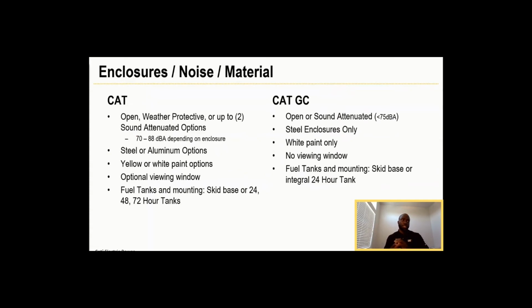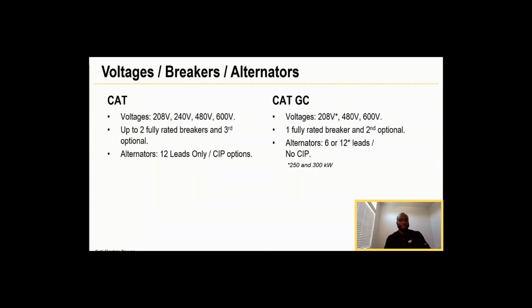On our fuel tanks, we see that the vast majority of North America's requirements, especially in the bid-spec world, usually concern tanks. That is either skid-based or a 24-hour tank available with the CAT GC product. With our traditional CAT product from the factory, you can get 24, 48, or 72-hour, and in some cases a 660-gallon tank as well. But if you're looking for something more or less than that, please contact your local dealer, as dealers have the capability to offer whatever customization you need.